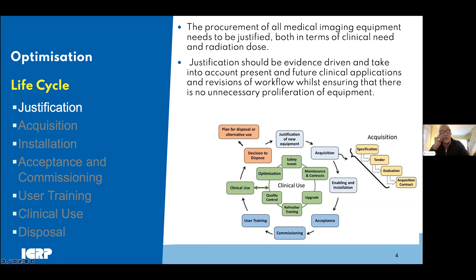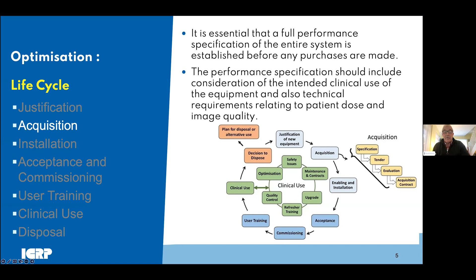The next stage is acquisition, or what you might call procurement, which itself has several components, as you can see from the diagram. It's essential that the procurement team think about the performance specification of the entire system before buying anything. They need to know what the intended use is, how it's going to be used operationally, and what the requirements are in terms of dose and image quality. And the supplier, in turn, should be able to demonstrate that what they're offering meets the specified needs. And of course, all this needs to be documented.